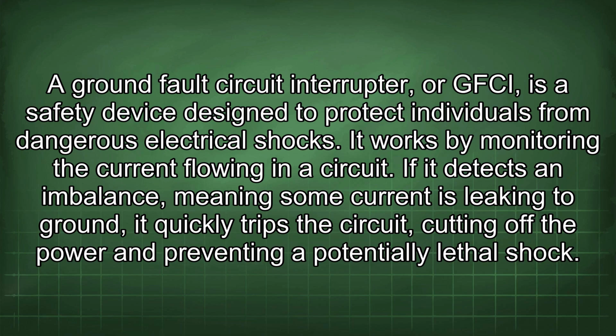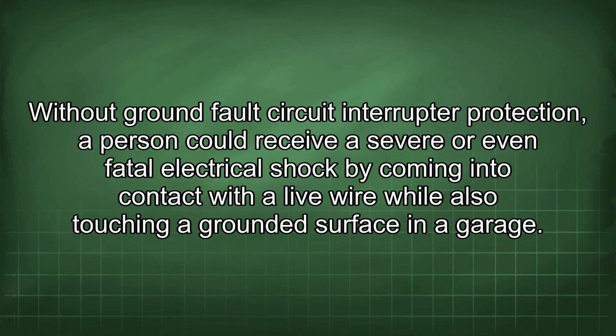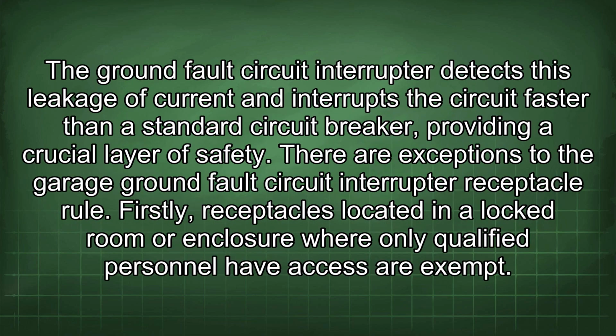dangerous electrical shocks. It works by monitoring the current flowing in a circuit. If it detects an imbalance, meaning some current is leaking to ground, it quickly trips the circuit, cutting off the power and preventing a potentially lethal shock. Without ground fault circuit interrupter protection, a person could receive a severe or even fatal electrical shock by coming into contact with a live wire while also touching a grounded surface in a garage. The ground fault circuit interrupter detects this leakage of current and interrupts the circuit faster than a standard circuit breaker, providing a crucial layer of safety.